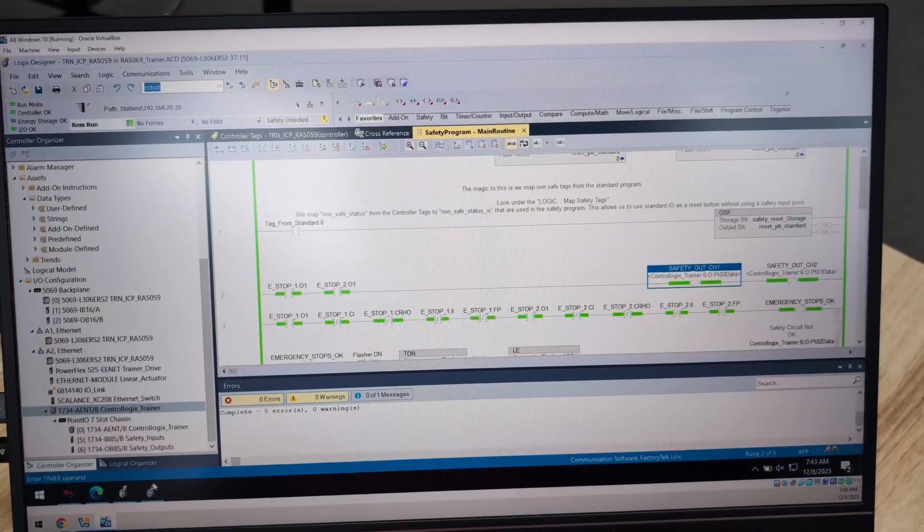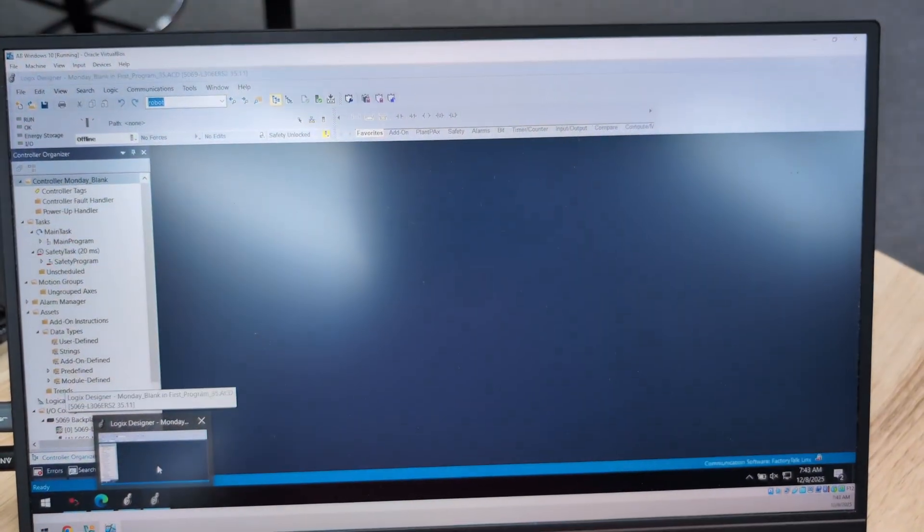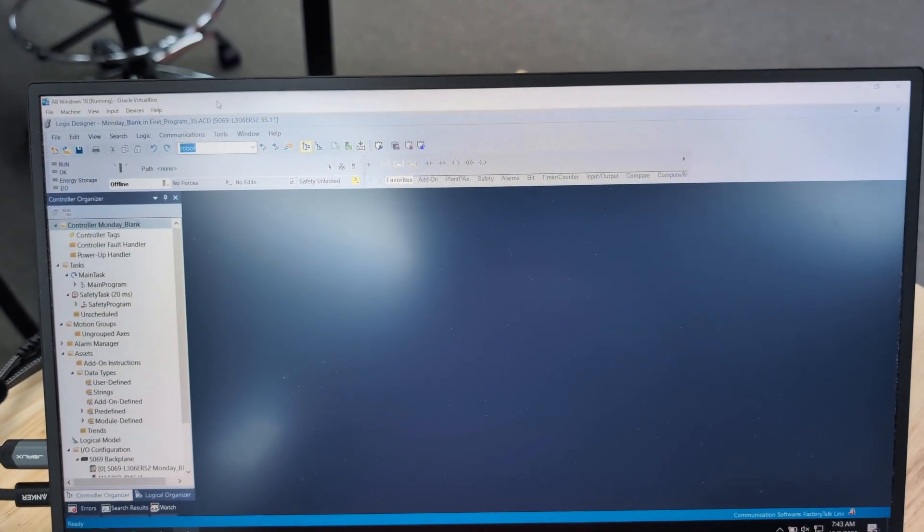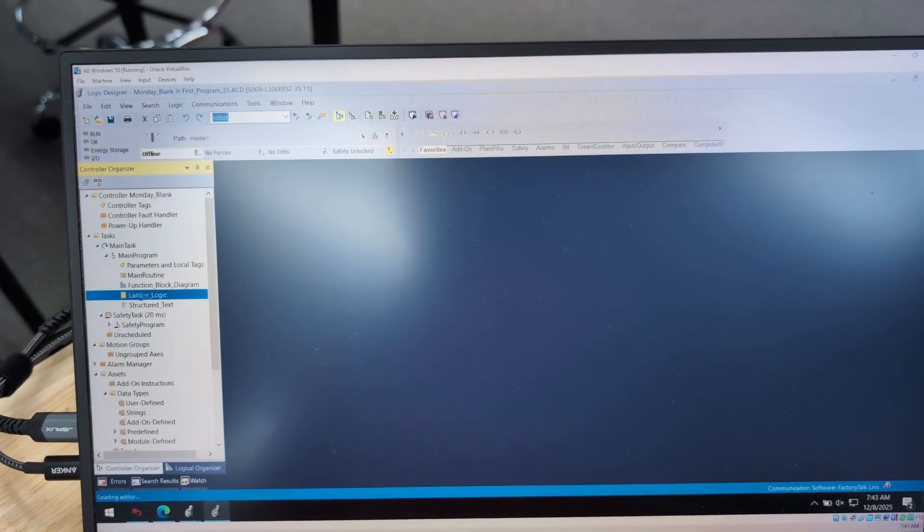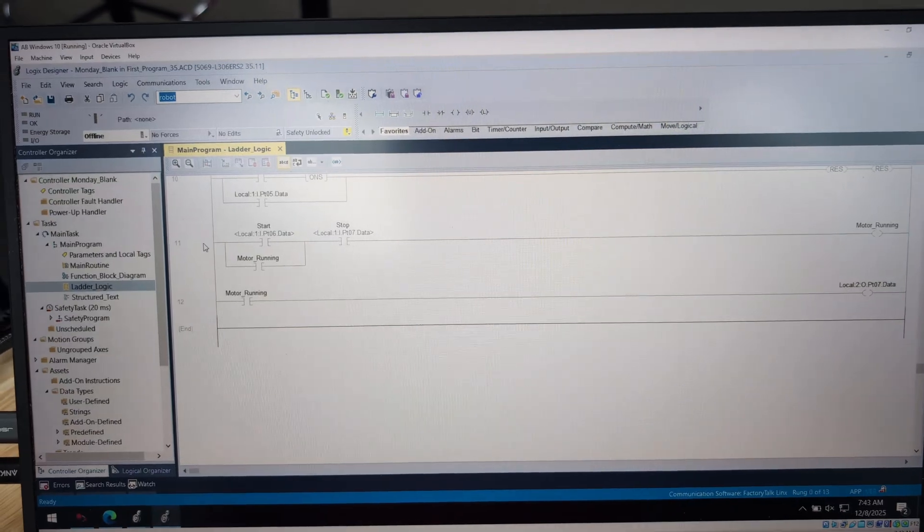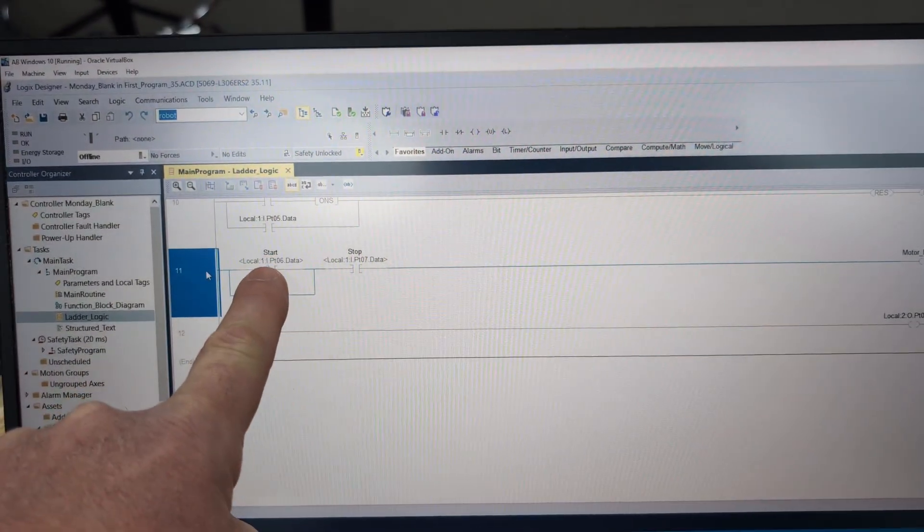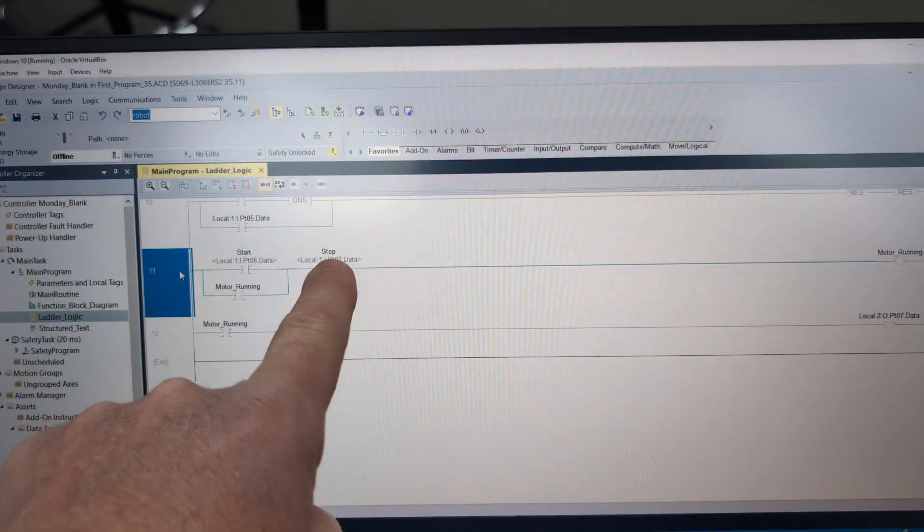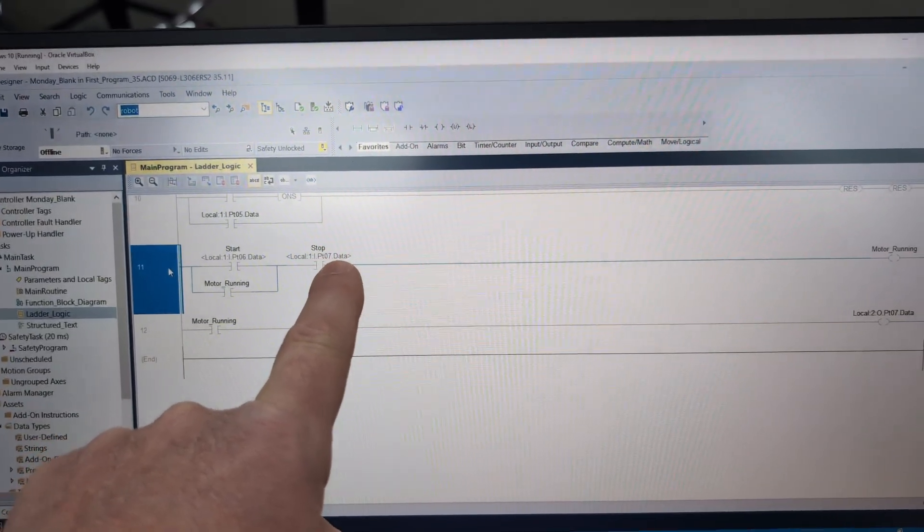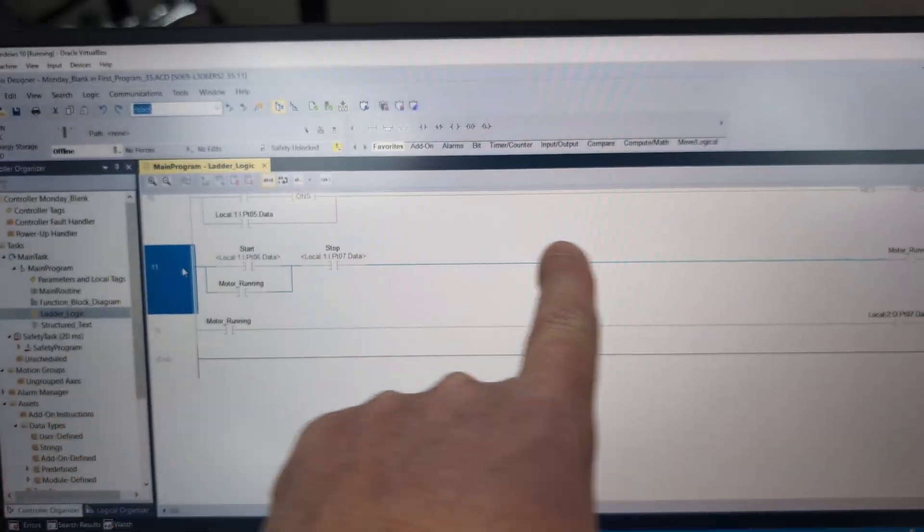Now going back to the poorly named aliases that John was alluding to, this is a Rosetta Stone program we do. Actually, it's the same program in ladder logic, function block, and structured text. And so if we go to the ladder logic version, and we go down and look at rung 11, then we have start, which is an alias for local:1:I PT06. And we have stop, which is an alias for local:1:I PT07. And then we have motor_running, which is a base tag. And arguably, this is fairly understandable.